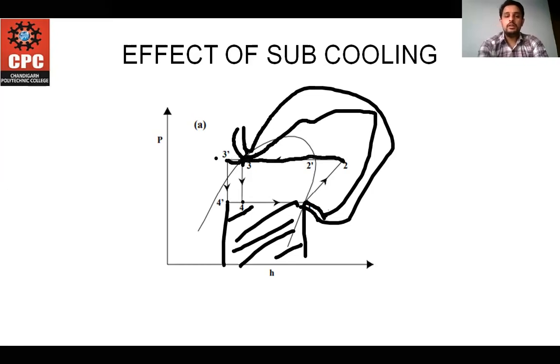We are reducing the temperature of the refrigerant coming from the condenser with the help of refrigerant coming from the evaporator, because the refrigerant coming out of the evaporator has quite a low temperature, and with the help of this we are cooling the refrigerant coming out of the condenser to a little bit lower temperature.